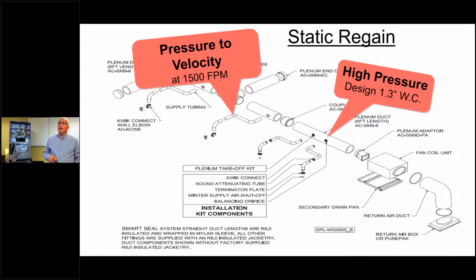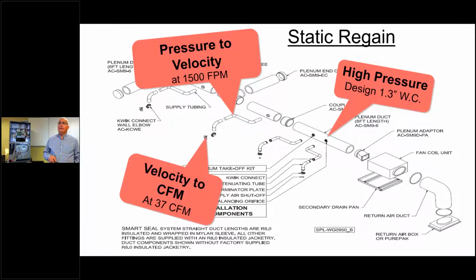All right, so you can see our high velocity that's coming out, all right? And what we want to attain is at least 30 CFM an outlet. 37 CFM is quite attainable. And what will happen is if we start to add more and more outlets based on the length of the 2-inch drop coming off the plenum to get to the room, okay? Then we have to make sure we've got proper placement in the room, and we'll need to do that to keep the CFM up. So what am I talking about there? Basically, if we go over 15 feet, we start to lose CFM on those 2-inch drops.